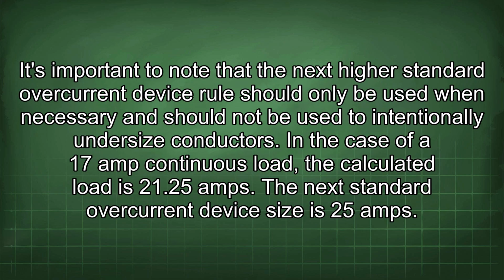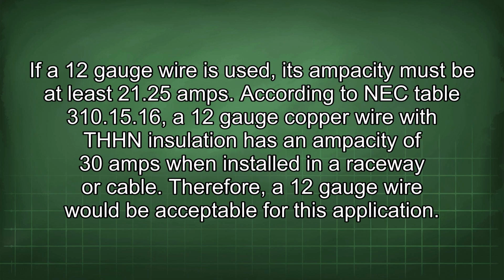It's important to note that the next higher standard overcurrent device rule should only be used when necessary and should not be used to intentionally undersize conductors. In the case of a 17 amp continuous load, the calculated load is 21.25 amps. The next standard overcurrent device size is 25 amps. If a 12 gauge wire is used, its ampacity must be at least 21.25 amps. According to NEC Table 310.15.16, a 12 gauge copper wire with THHN insulation has an ampacity of 30 amps when installed in a raceway or cable. Therefore, a 12 gauge wire would be acceptable for this application.